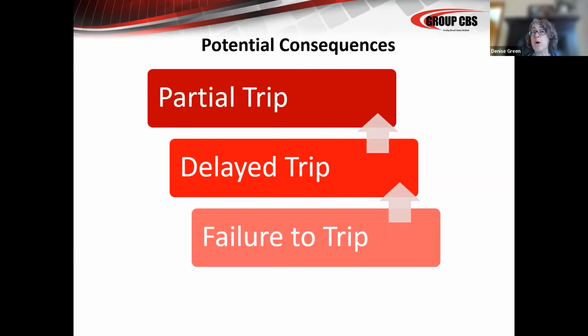If a vacuum interrupter is in good shape, then it's going to interrupt and everything is going to be fine. If your vacuum interrupter is not in good condition, and you have either close to the end of life, where you have too many molecules of contaminant in that interrupter, or the interrupter has already failed, then you can have that issue with the partial trip. In vacuum, it doesn't matter. The gap is so small that as long as the breaker opens, it's not going to be an issue.